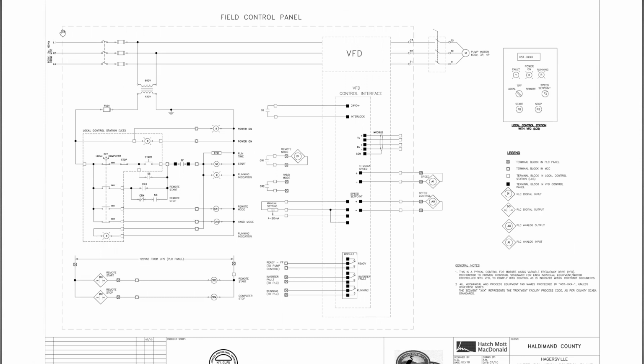So here you have a VFD that runs off of 600 volts. There's a 600 volt to 120 volt transformer. This would be inside that electrical panel. It will step down the 600 volt voltage to the control of this VFD, so this pump. So the pump, then the motor for the pump is connected to the VFD. So you have 600 volts coming in, and then you have the control voltage going out that could be varied to run this pump anywhere from technically 1 hertz all the way up to 60 hertz.